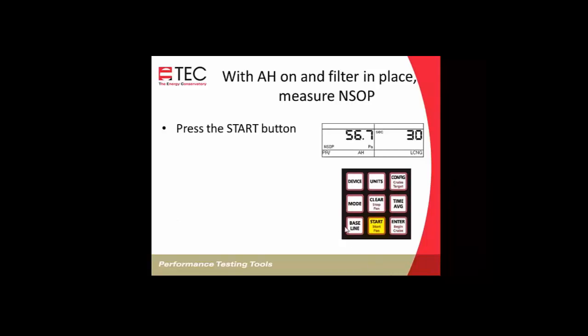So the start button is in the middle here. Once we push start, we'll see the seconds start to count off. So these are seconds, and it'll count off 1, 2, 3, 4, 5. And once the pressure on the left becomes stable, this is going to display a long-term averaging. So over time, it'll get more and more stable. And once it stays the same for 3 or 4 seconds, we can push enter, and then that enters the normal system operating pressure into the gauge.